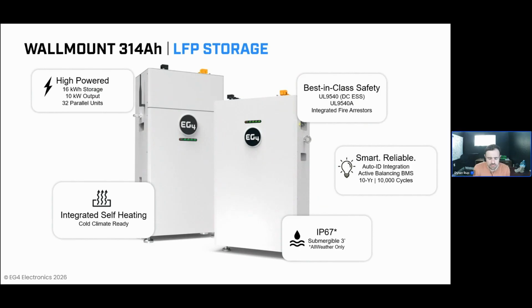Now, the unit, as you'd expect, does pack considerable energy capacity and power delivery in a relatively small footprint. Each one of these units with 314 amp hours of capacity stores up to 16 kilowatt hours of energy and will support 10 kilowatts of continuous AC output. For optimal performance, we generally recommend that at least 2 of these units are deployed per FlexBOSS inverter, with up to 32 supported in a single deployment.